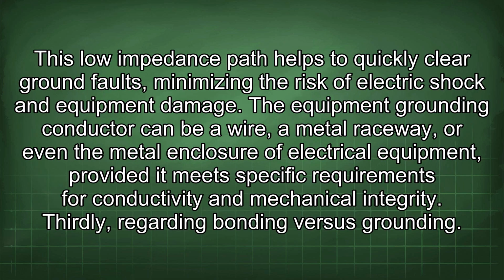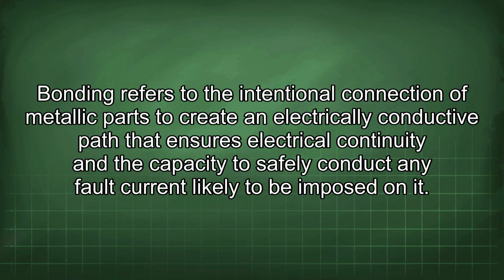This low impedance path helps to quickly clear ground faults, minimizing the risk of electric shock and equipment damage. The equipment grounding conductor can be a wire, a metal raceway, or even the metal enclosure of electrical equipment, provided it meets specific requirements for conductivity and mechanical integrity. Thirdly, regarding bonding versus grounding. Bonding refers to the intentional connection of metallic parts to create an electrically conductive path that ensures electrical continuity and the capacity to safely conduct any fault current likely to be imposed on it.